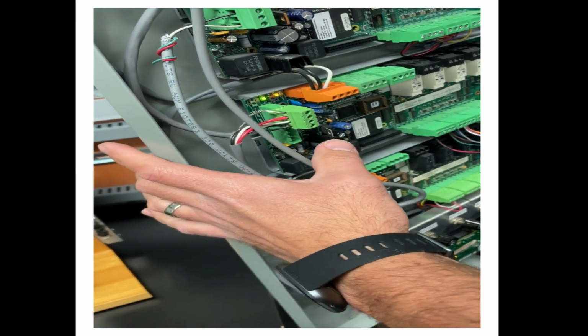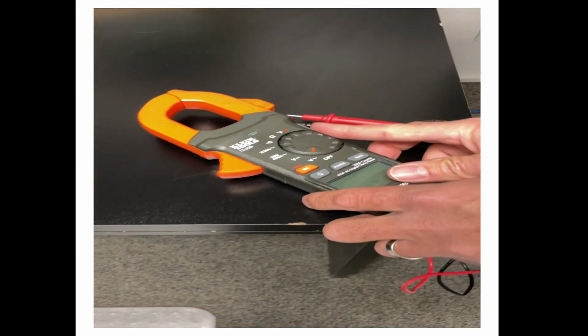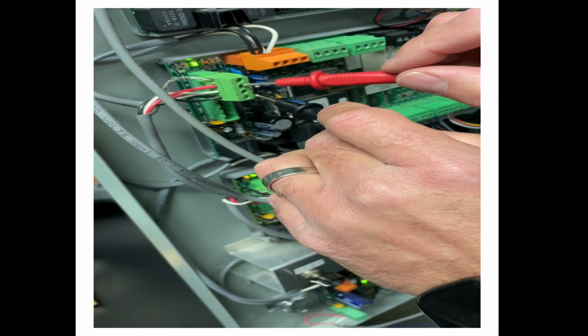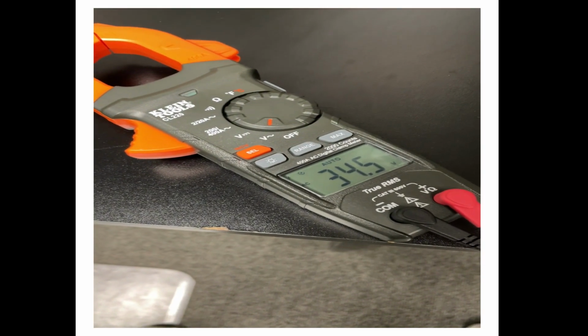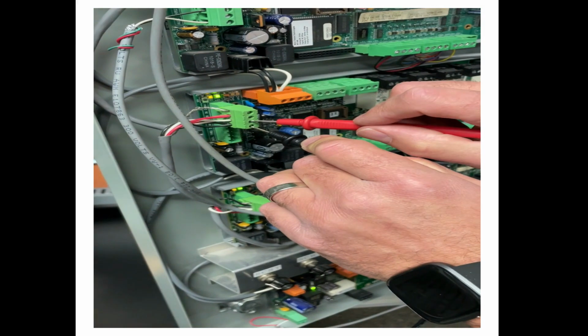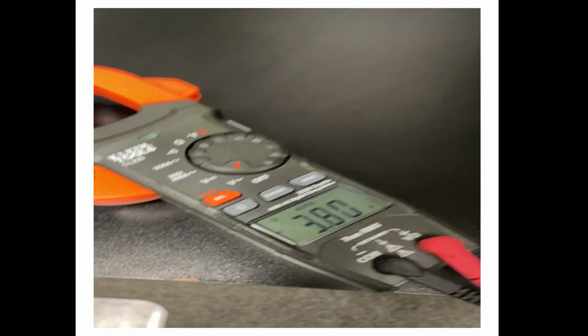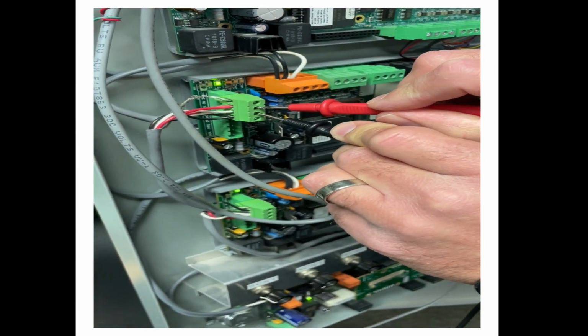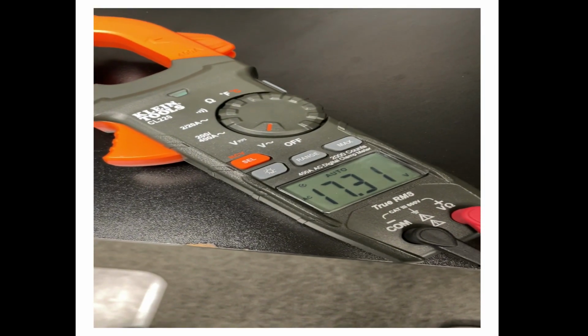Please remember that the MT500 boards are powered with a center tap transformer. It can be a 24 volt or a 32 volt transformer. In this case, it is 32 volt, so look for 32 volts plus or minus 10% or 16 volts plus or minus 10%.